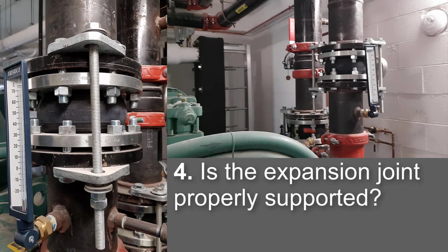Is the expansion joint properly supported? In this case, the short length pipe below the joint is supported by its connection with the chiller, and the pipe above is supported by hanger rods to the structure above. It is best to minimize the amount of pipe between the chiller and the joint since the chiller connections are not designed to take much load. Since the control rods are loose on the one joint, that one is definitely okay. The joint isn't supporting more weight than its own. I would guess that even though the rods are not loose on the second joint, it's probably okay as well since there is very little pipe between it and the chiller connection. So we'll call this okay.